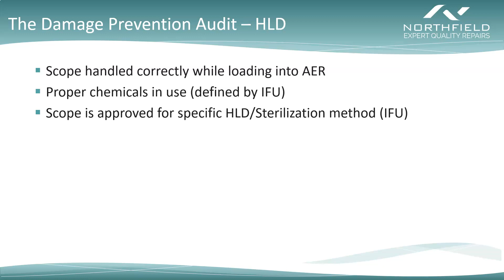Now, when we come to the high-level disinfection phase, we want to make sure that the scope is being handled correctly while it's being loaded into that automatic endoscope reprocessor. Now, keep in mind to follow the manufacturer of your AER's IFUs for how to properly load a scope. We also want to make sure that the proper chemicals are in use, again defined by that manufacturer's IFUs. And we want to make sure that the scope that you're processing is approved for those specific high-level disinfection or sterilization methods. Again, that will be defined by your IFUs. Again, one thing that we want to keep in mind is regardless of which process you're using or which manufacturer you're using, you want to use certain care and handling methods while you're loading the scope and while you're unloading the scope.